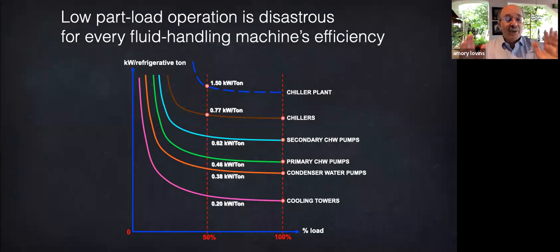Conversely, as we saw in Buildings Lecture 2C, a really optimized chilled water system can more cheaply achieve 0.44 whole system kilowatts per ton at the design hour in Singapore. In other words, less than a fifth of the 2.43 kilowatts per ton shown here at half load. And I just see that I misspoke. I referred to the 1.5 kilowatts per ton as a typical chilled water system. It's not the system, it's the chiller plant. So you have to make sure you're adding up everything.